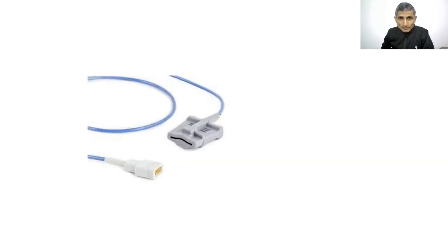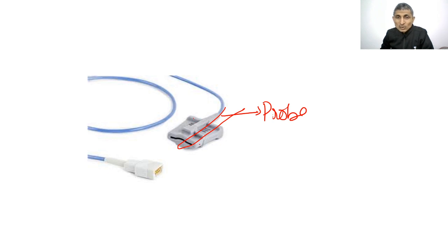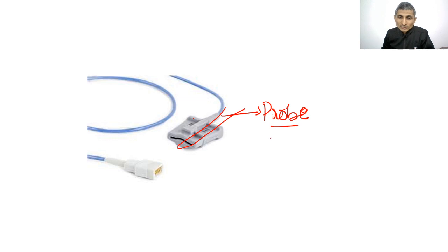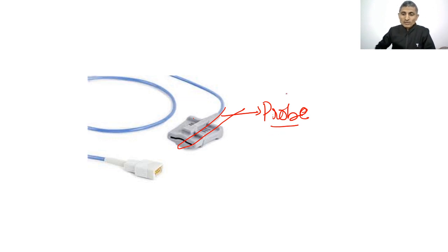This is a probe of the pulse oximeter. The finger is inserted into this part and oxygen saturation of arterial blood is measured. The pulse oximeter senses only the pulsatile blood, which is why it measures arterial oxygen saturation.